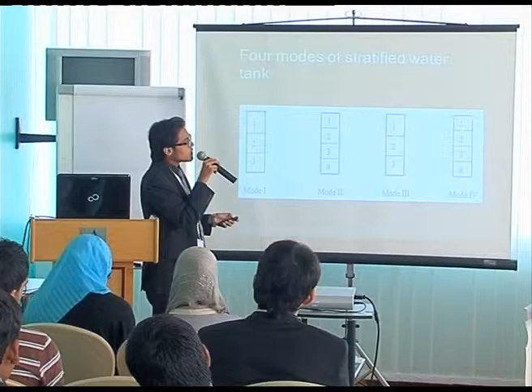This is because when sunshine is low, in the early morning or evening as the sun rises or sets, we connect the auxiliary heater in parallel at the top portion. So when sunshine isn't sufficient, we run the auxiliary heater and heat only a small portion, about a quarter of the total storage tank, meaning we don't have to heat the whole tank to keep the system operational.